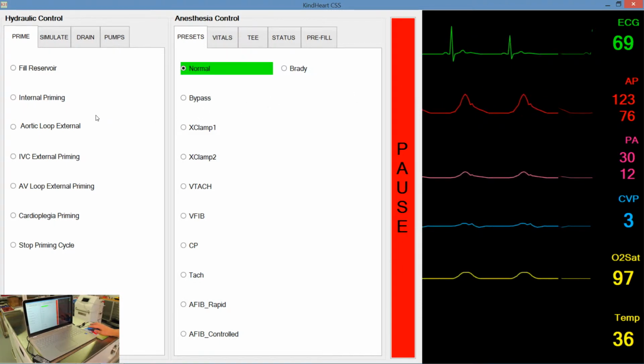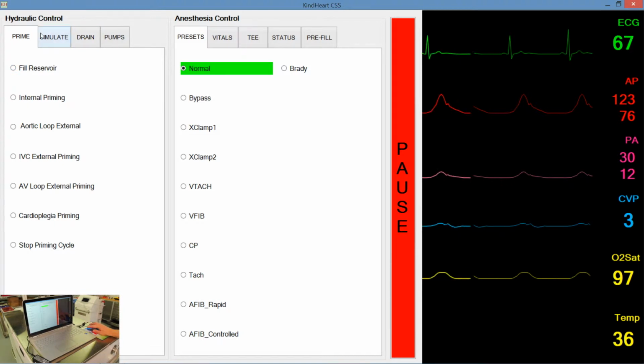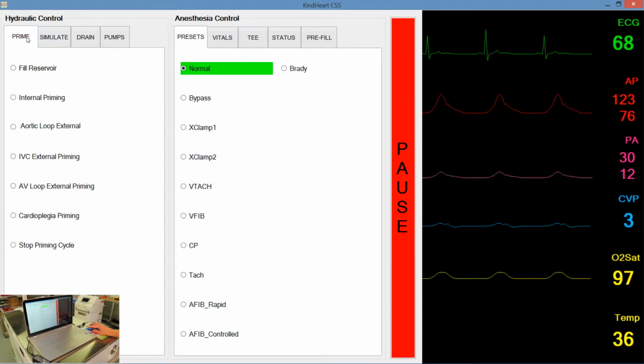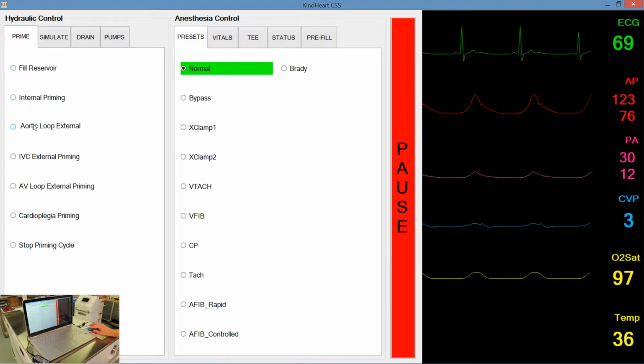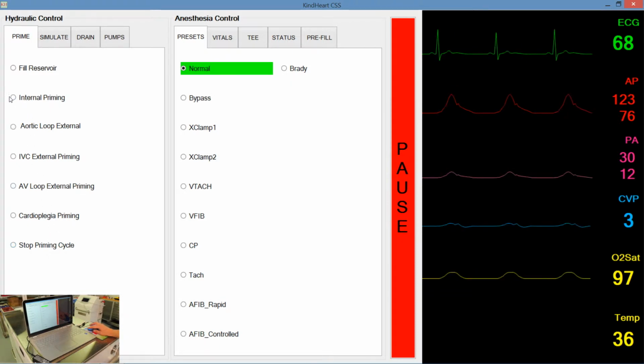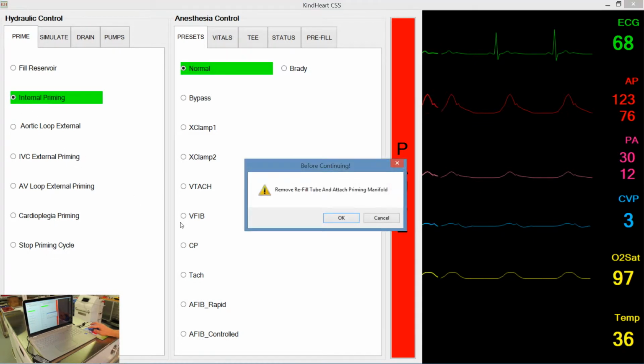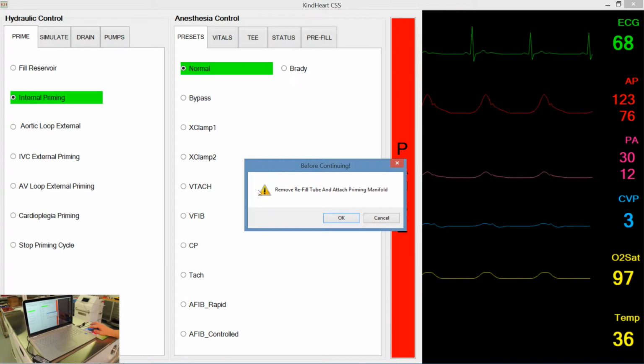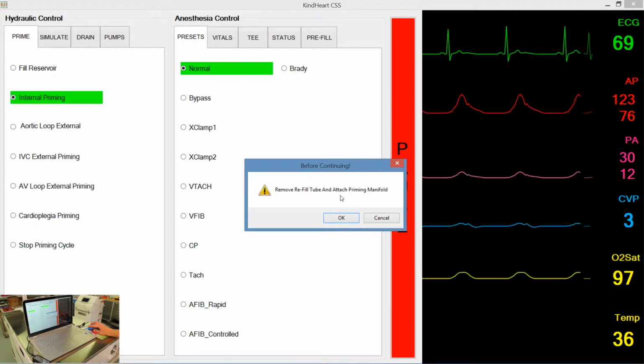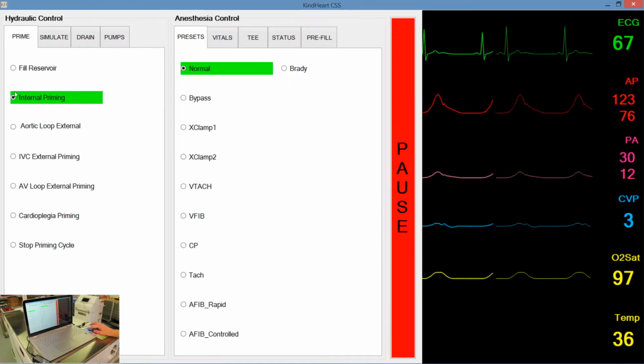In terms of the hydraulic controls, what this screen controls is the internal pumps and valves that do a variety of things for the device. The Prime tab, through a drop-down list, enables you to fill the reservoir, internally prime it, prime the external aortic loop, the inferior cava, and the different levels of tubes. Now I'm going to click internal priming to show you something. When I click that, this status will come up and it'll say remove the refill tubes and attach the priming manifold. This is to remind you of how to hook the device up. Once you do that, you click OK and the machine will go from there.